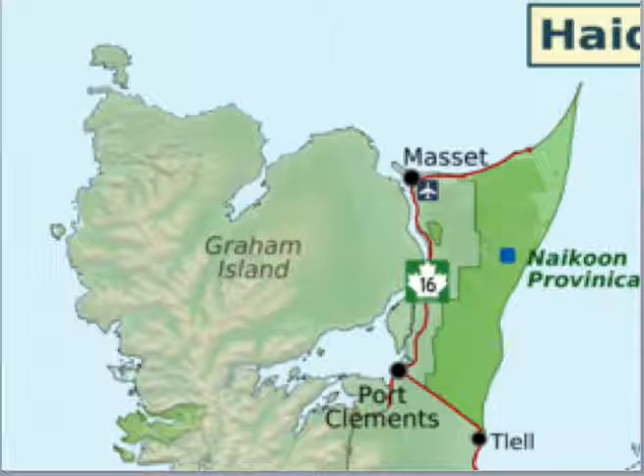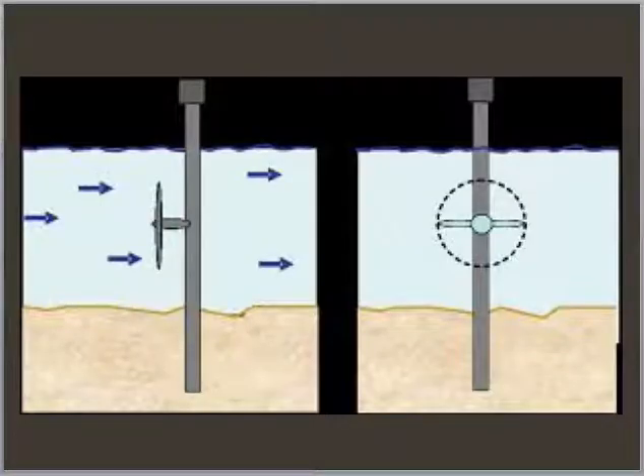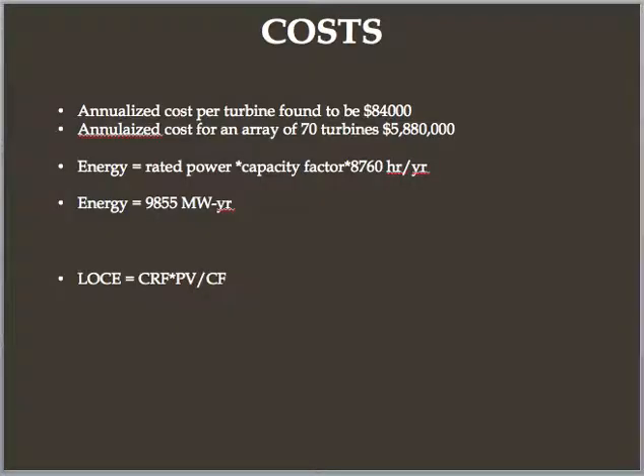More turbines could potentially be deployed, but let's look into the levelized cost to get an idea of how tidal compares to diesel generation. The capacity factor is low for tidal energy as tides do not offer continuous flow. A capacity factor of 0.25 will be used. This is an average value taken from various tidal generation sites from around the world such as Wales, Scotland, and France. Making the assumption on cost and maintenance, an annualized cost of $84,000 per turbine is found. This translates to an equivalent annual cost of about $5.88 million for the entire array.